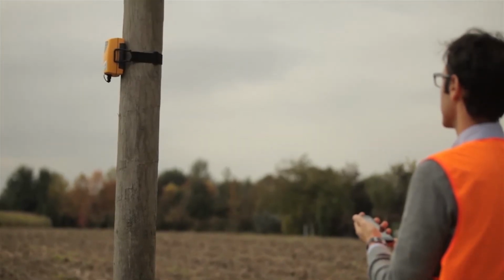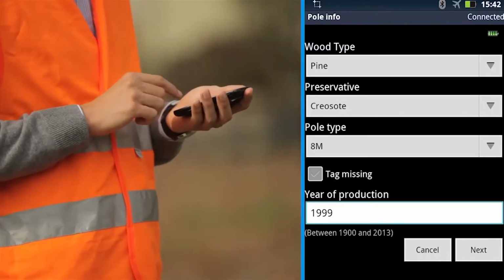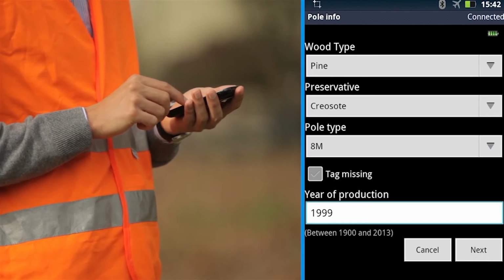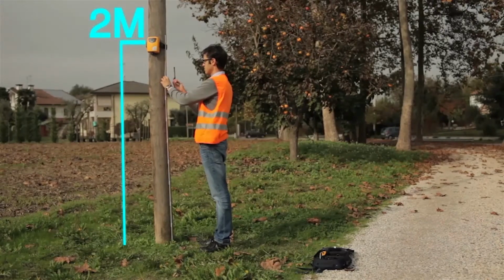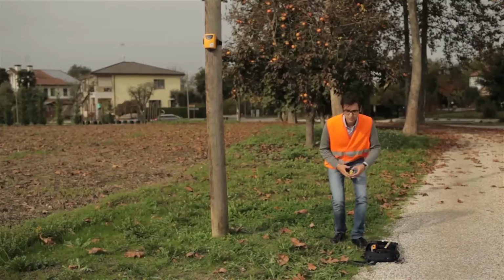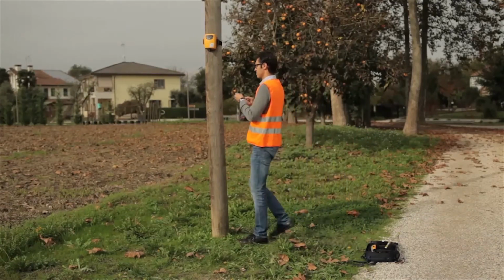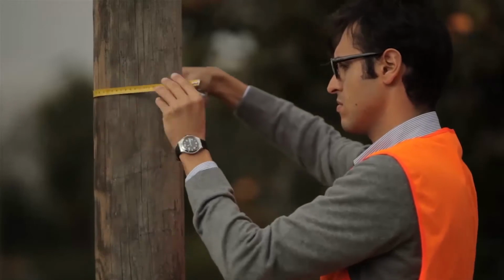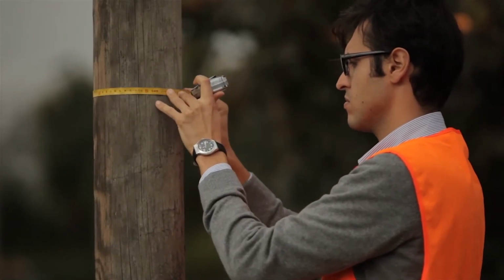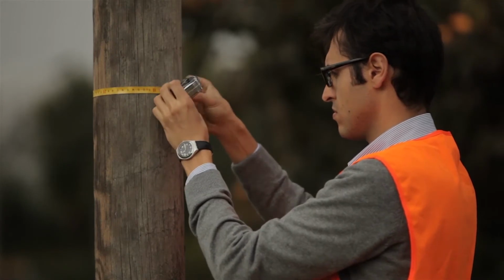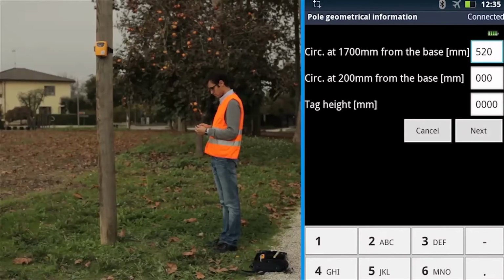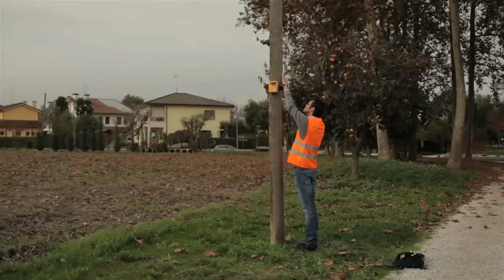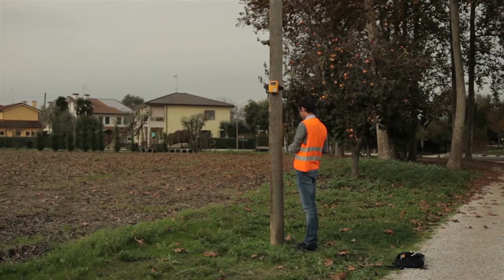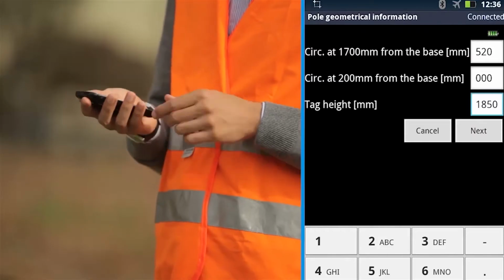Look at the pole tag, find out the pole characteristics, pine, creosote, pole type, pole year, and enter these details into the smartphone. Check that the device is fixed at 2 meters from the ground. Measure the circumference at 1.7 meters and input the information in the smartphone. Measure the tag height from the ground and enter the information in the smartphone.